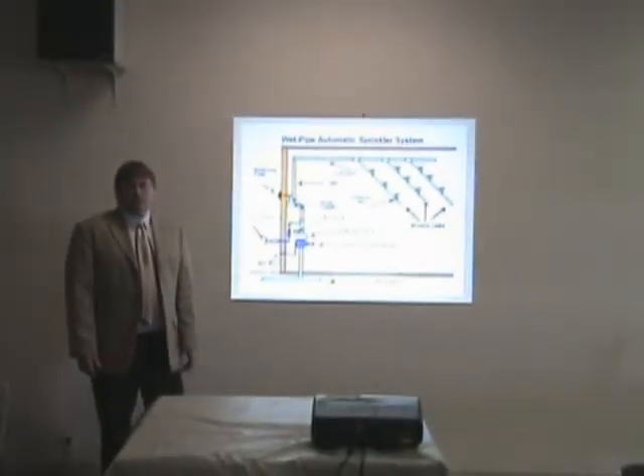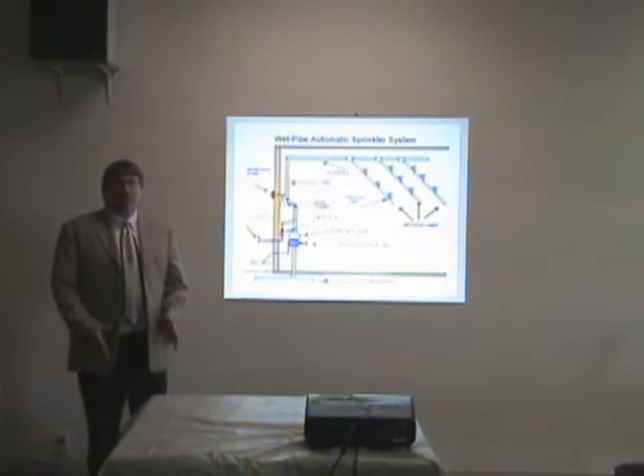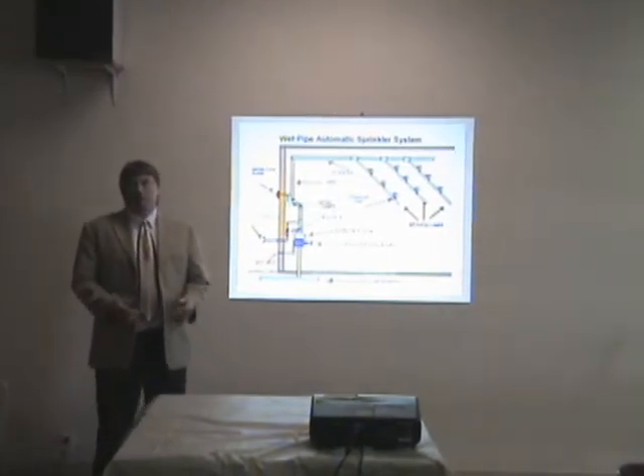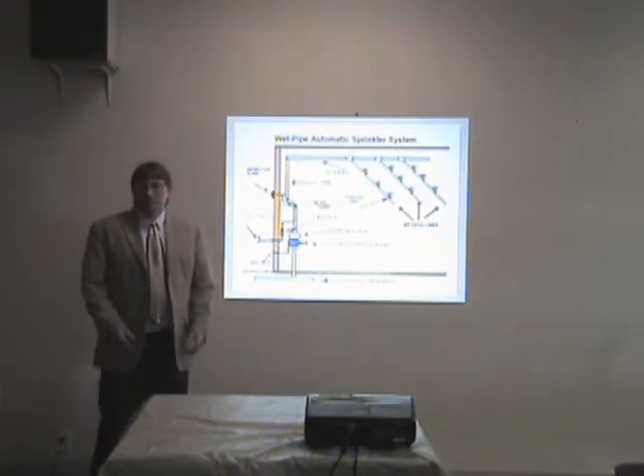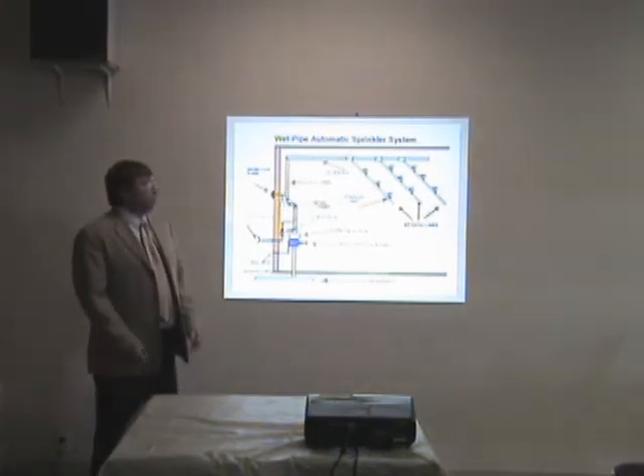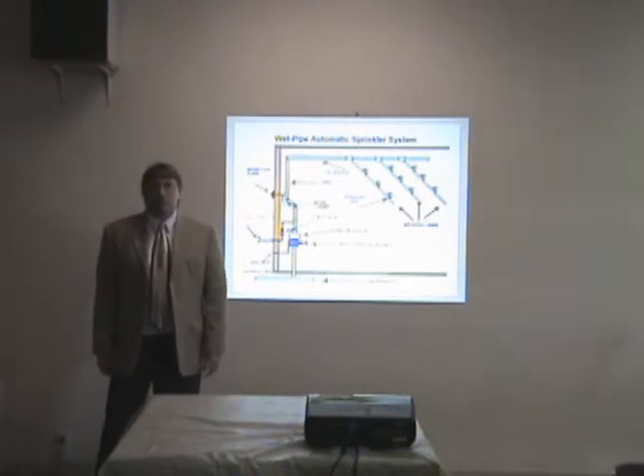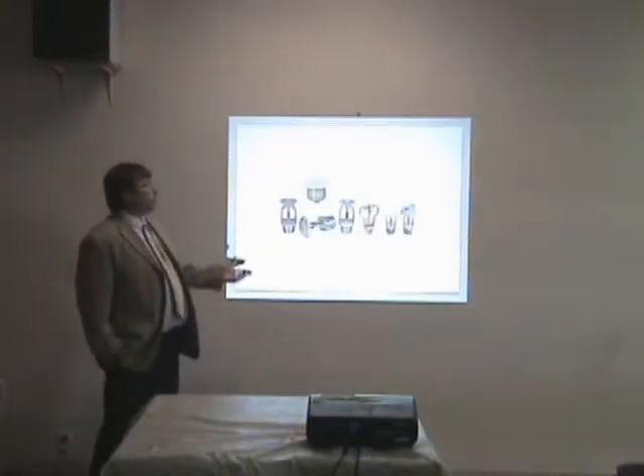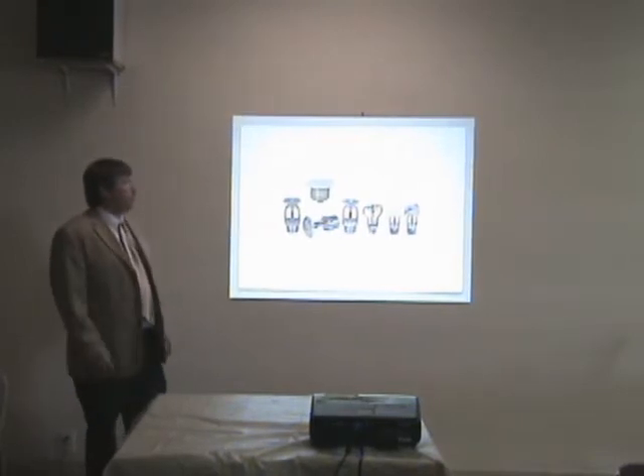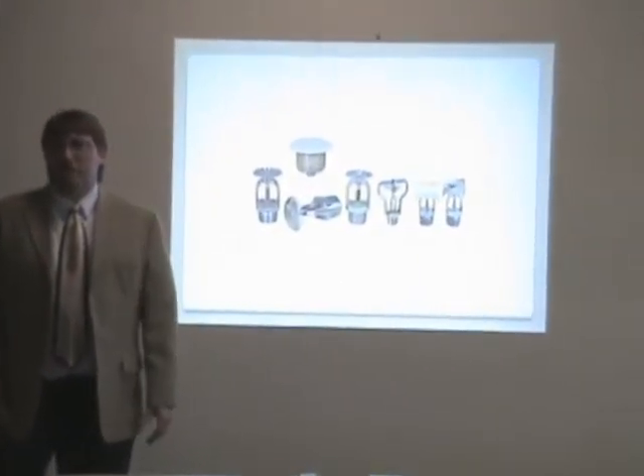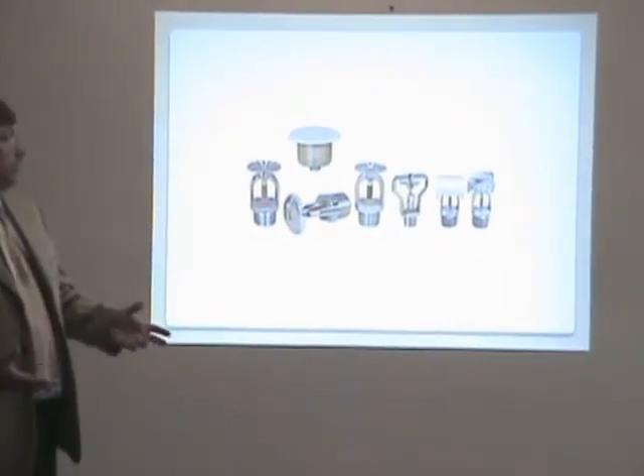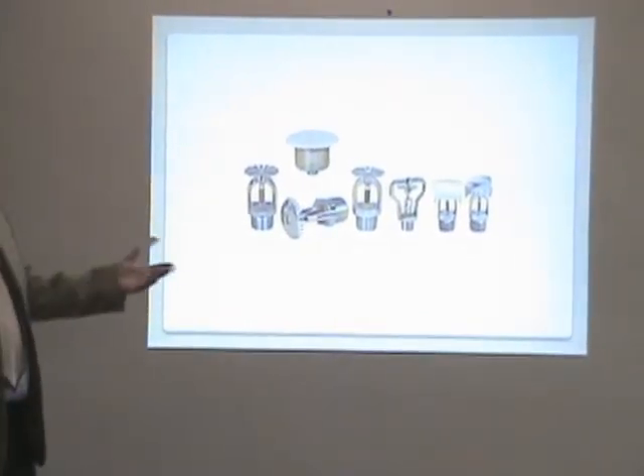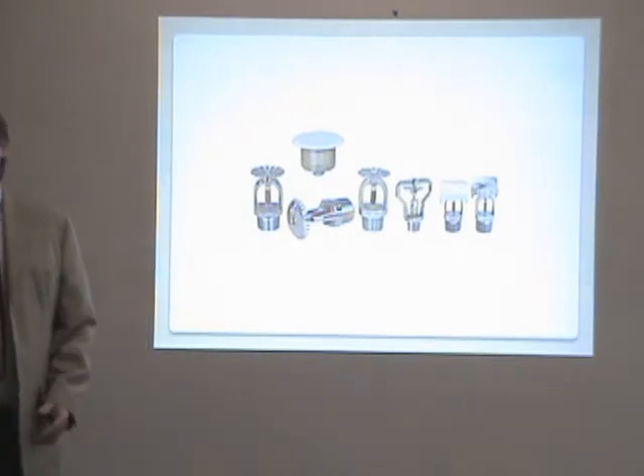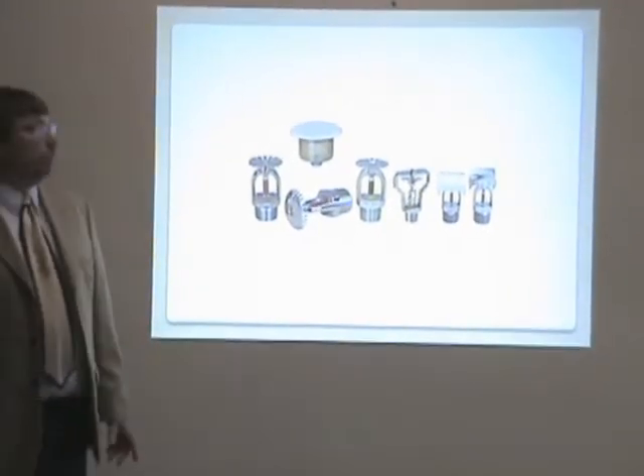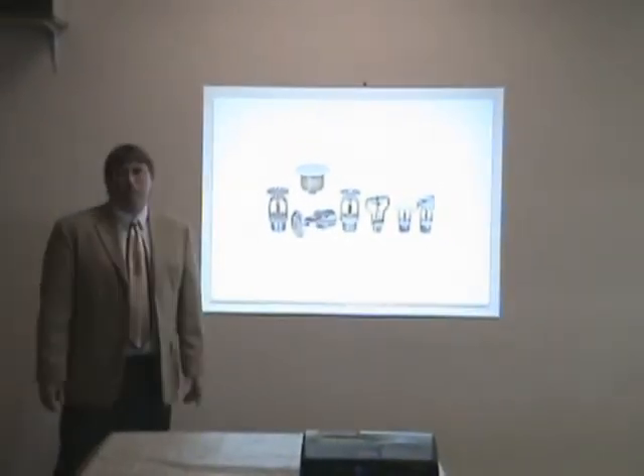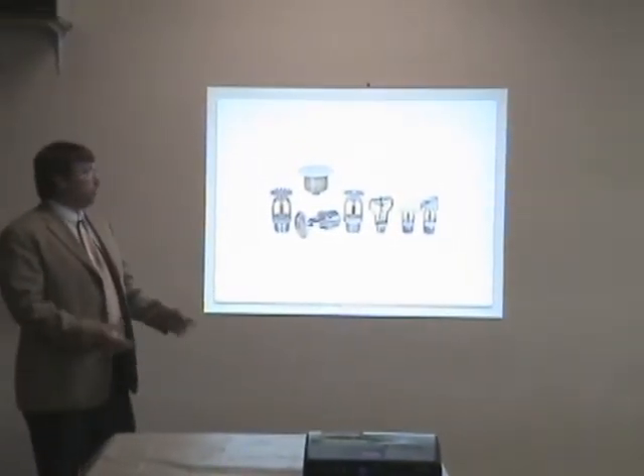Wet pipe sprinkler systems have sprinkler heads that are designed with a heat-sensitive element that will respond to the heat of the fire. Whenever there's a fire in the area, whenever there's heat, the sprinkler head will open at a predetermined designed temperature. There are all types of sprinkler heads available, and each one has a specific purpose and a specific design for a specific job. But they're all basically the same in that they have a heat responsive element that opens whenever the heat reaches a predetermined point that the temperature rating is set for.